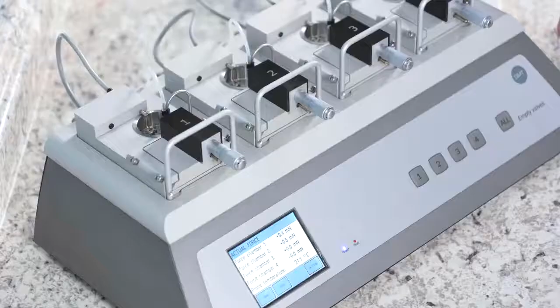The first thing you need to do is remove the tissue from your chamber. Then you will take 8% acetic acid and fill the chamber to the top. Make sure to leave your gas bubbling on. If you turn the gas off with your buffer still in the chamber, the buffer over time will start to harden and block that line.